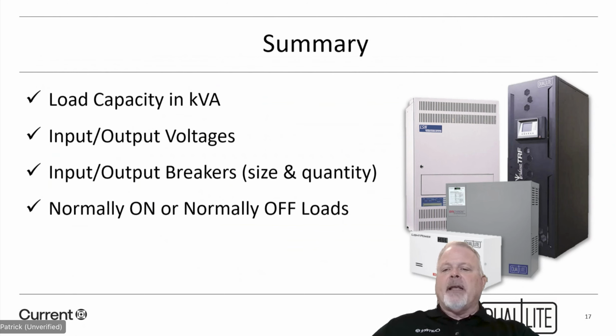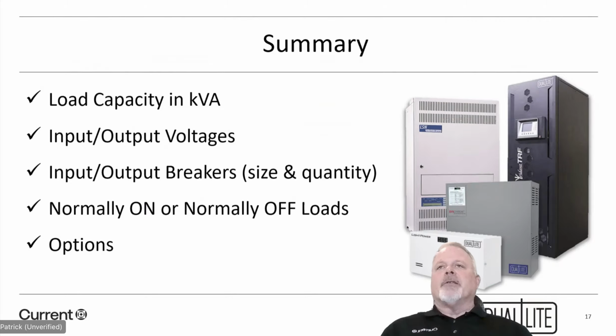In summary, we talk about load capacity and kVA, input output voltage, input output breakers, size and quantity. They do vary. I think they go anywhere from 10 up to, I believe we offer up to 100. Normally on, normally off loads, and any of the options that we discussed. Why do we want an inverter versus some of the other UL equipment that I've already mentioned? An inverter is a centralized system. It will cost the customer long-term less money to run and operate than some of those other systems. And they won't have to worry about necessarily failing an inspection because that information is recorded automatically in the lighting inverter itself.